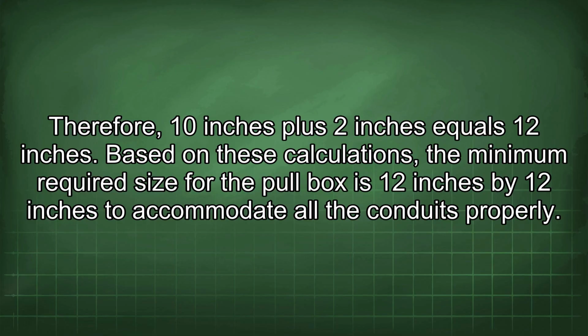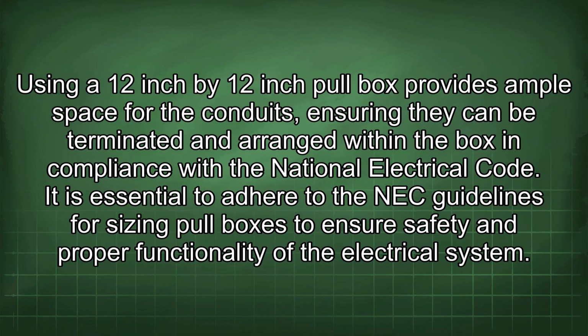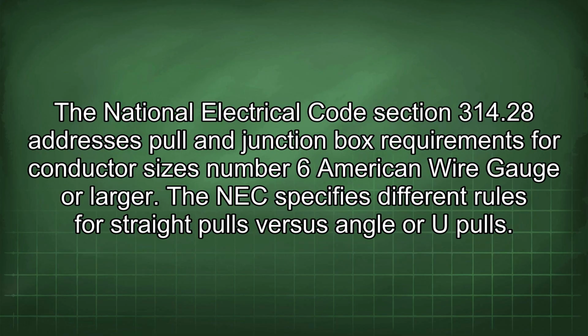Based on these calculations, the minimum required size for the pull box is 12 inches by 12 inches to accommodate all the conduits properly. Using a 12-inch by 12-inch pull box provides ample space for the conduits, ensuring they can be terminated and arranged within the box in compliance with the National Electrical Code. It is essential to adhere to the NEC guidelines for sizing pull boxes to ensure safety and proper functionality of the electrical system.